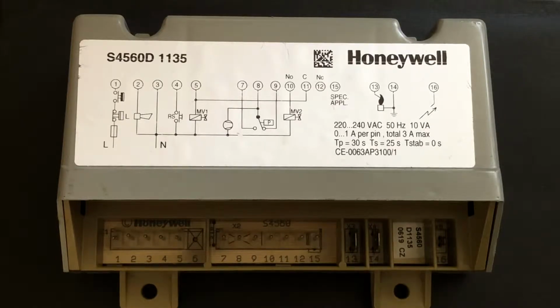So when the fan starts, this connection is connected to a differential pressure switch, which I sometimes call a proving switch. It tells us that the fan works because we have positive or negative pressure in the fan. It depends on where the little tubes that sense the air are mounted. If they are mounted on the positive pressure side of the fan, then you read positive pressure. If they are on the negative pressure side, then you read negative pressure. I found multiple ways of wiring and multiple ways of locating the little clear tubes which attach the pressure switch to the fan chamber.